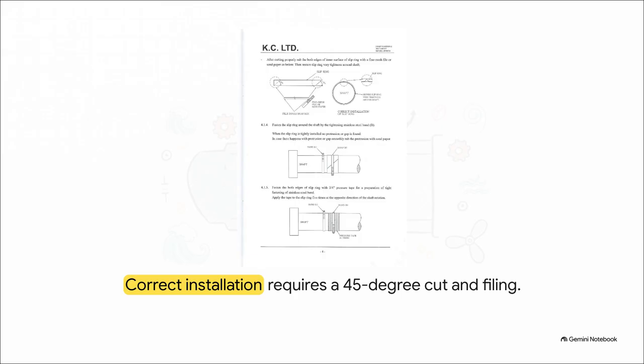That precise 45-degree cut and the careful filing of the inner surface to remove sharp points, that smoothing process is non-negotiable. If that joint isn't perfectly smooth, with absolutely zero protrusions or gaps, the slip ring is just going to chew right through those expensive silver graphite brushes in no time. A smooth track is literally the secret to a long, healthy life for the entire earthing system.